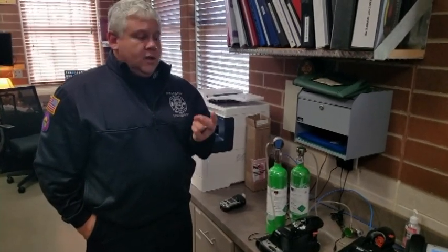Once it's done, you should have either a solid green light or you have a red. Green means you're good to go. Red means it's failed, okay? And like I said a moment ago, if you go through that step-by-step process where you bump it, and if it fails, it calibrates and it fails, and you repeat that one time, then at that point, please get in touch with me and I'll try to help you out.